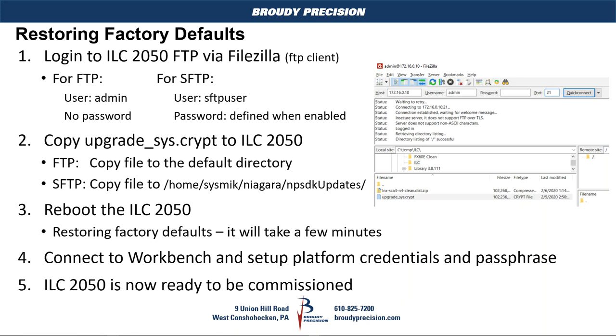It will take a few minutes for the controller to restore factory defaults. You'll see the LEDs cycling through a pattern over and over again. Eventually the PL LED should flash once every second, showing that the daemon has loaded. Once that happens, you can go into the ILC 2050 with platform to do your commissioning. Since it's restoring factory defaults, Workbench will first have you set up a new platform user — it removes the sysmik user — assign a password, and create a passphrase. After that you'd copy the license file, station, required modules, and core software.